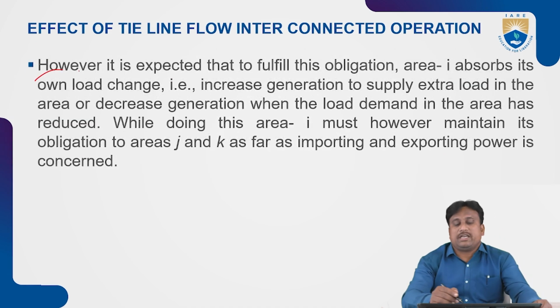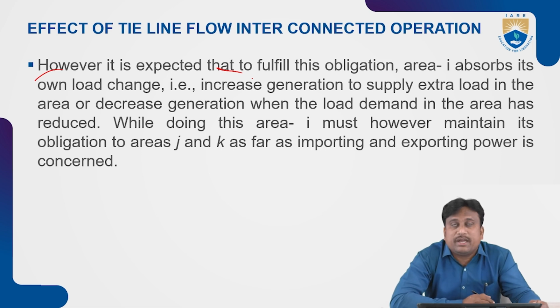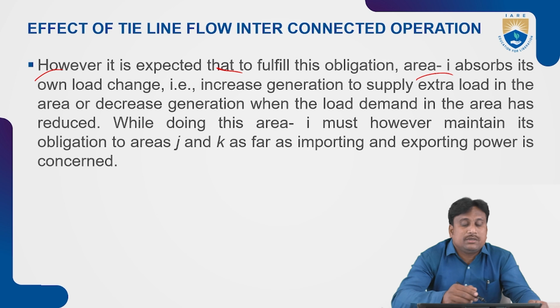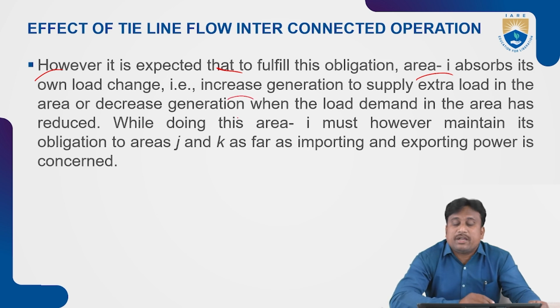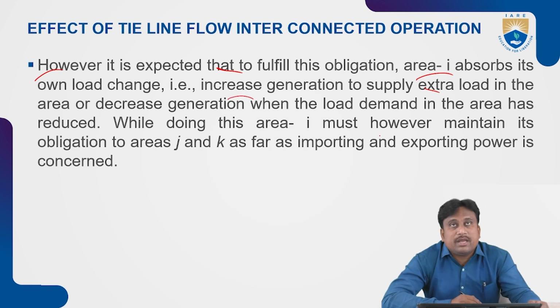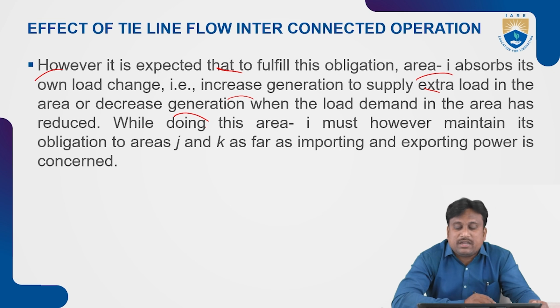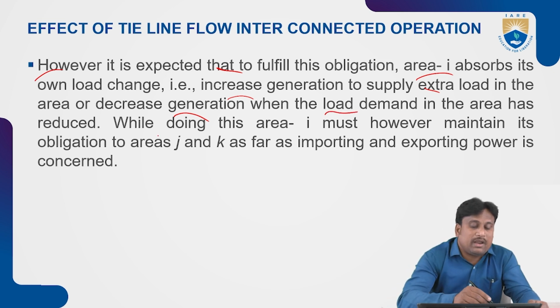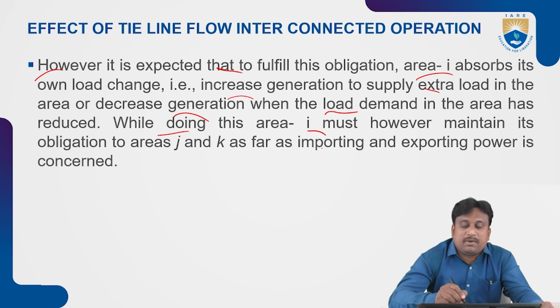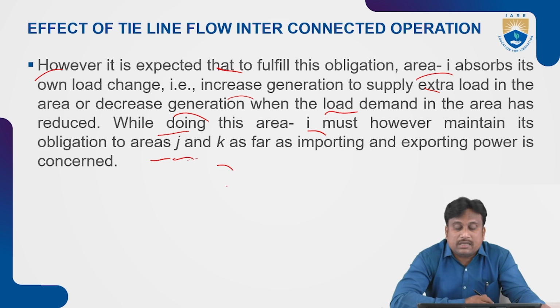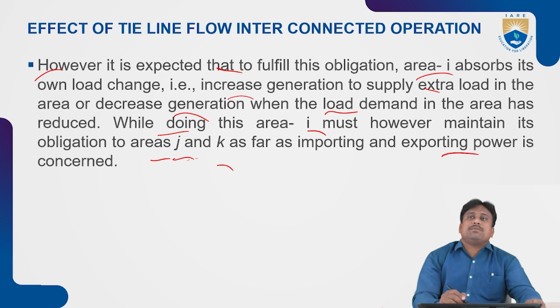However, it is expected that, to fulfill these obligations, area I is ready to absorb its own load change. So it may increase generation to supply extra load in the area, or it may decrease generation when the load demand in the area has to be reduced. While maintaining all these, the area must, however, maintain its obligation to areas like J and K as far as importing and exporting power to the connected regions or connected boundaries.